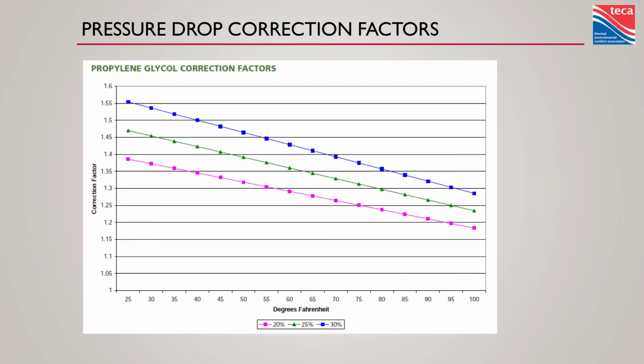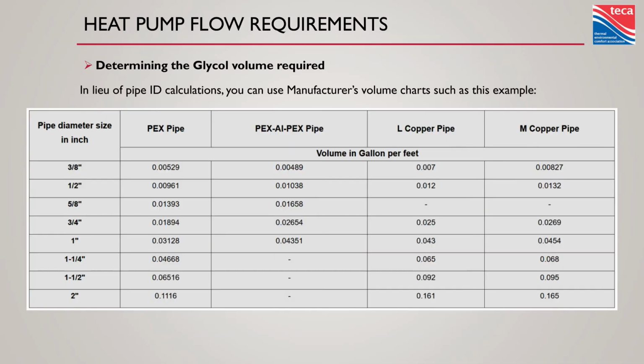Pressure drop is a much bigger one. That same 20% blended glycol at a 55 degree temperature outside is about 30% more pressure drop than 100% water. So again, you're going to want to make sure you're following these charts and going through to make sure your pump has been selected for these parameters, and your heat pump's going to get the flow it needs to have a nice long life.